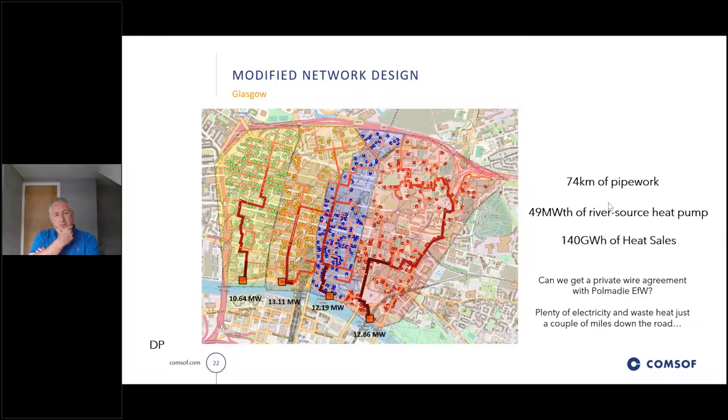The observant will notice that the right-hand area has extended further north - we stopped at Sauchiehall Street and have now extended up over Gilmorehill and up to the motorway, because that's the region the city was looking at, hence greater pipework. We're now up at 74 kilometres, with a greater level of heat demand and heat sales. We also started thinking around private wire questions - Polmadie is selling electricity to the grid for approximately 4.5 pence. What if there was a private wire from Polmadie down to this scheme, running the cable down the river to cut some costs? So there are lots of 'what ifs' that we've been asking.